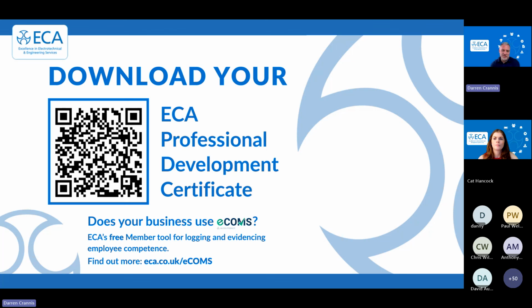Thank you, Christian. So to clarify on Christian's great question there for commercial cabinet sockets, for IT cabinets and bits like that: if you've got a TT supply, you still need to sort out your head end. You still need to sort out your fault protection. But your 30 milliamp protection, depending on how you install that cable, typically armoured, could be lost with the risk assessment. Thank you, Christian, for clearing that one up.